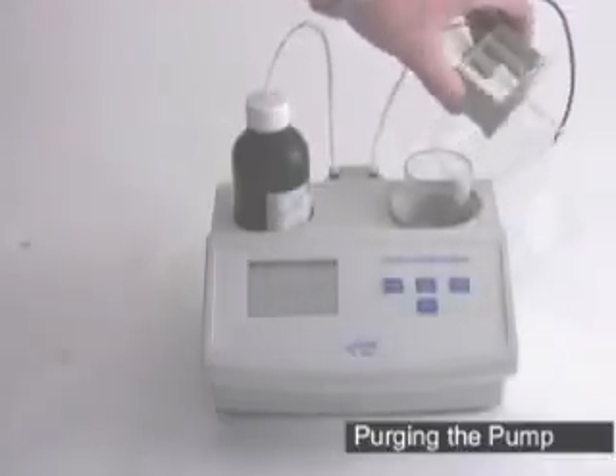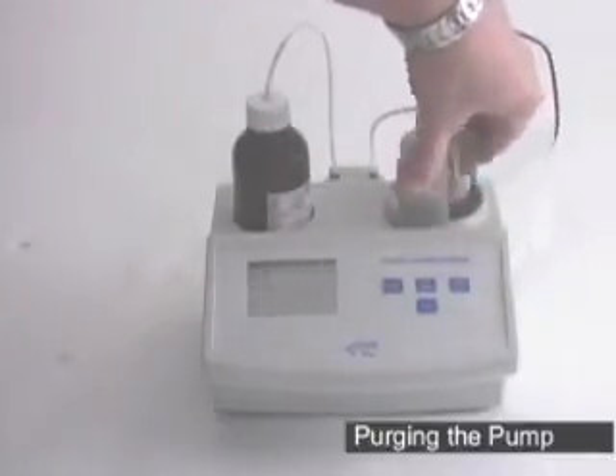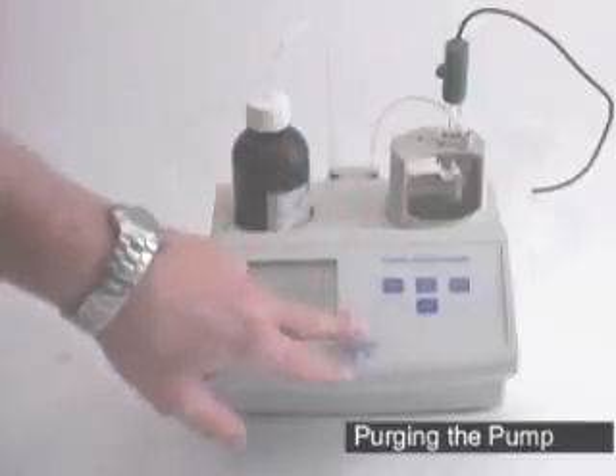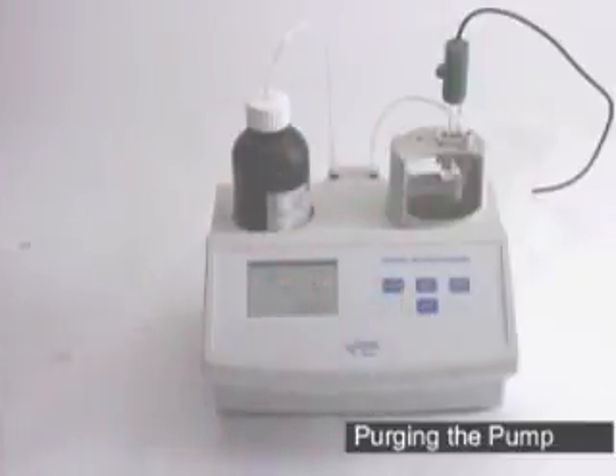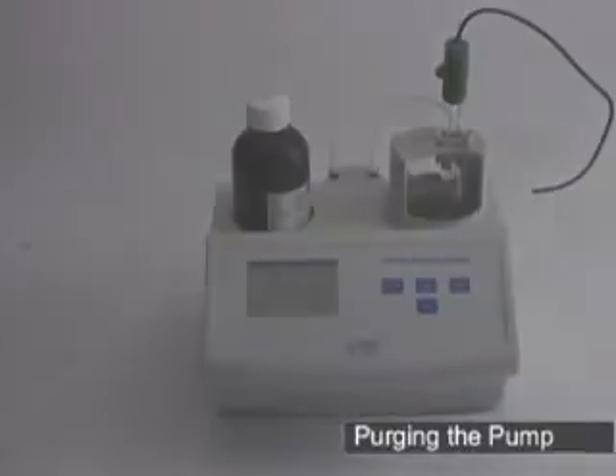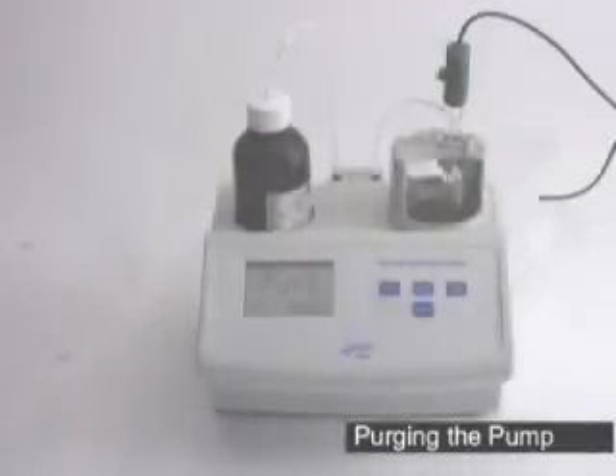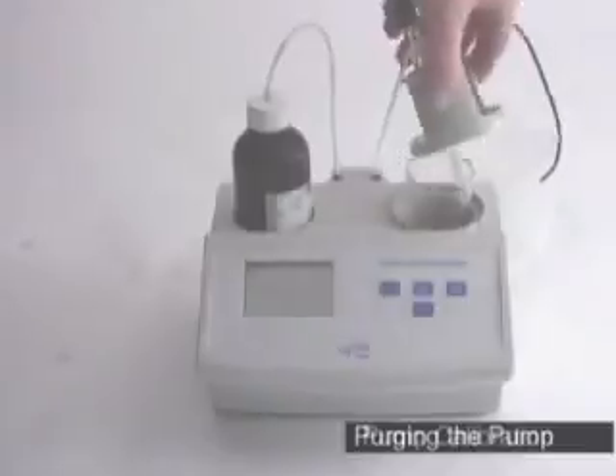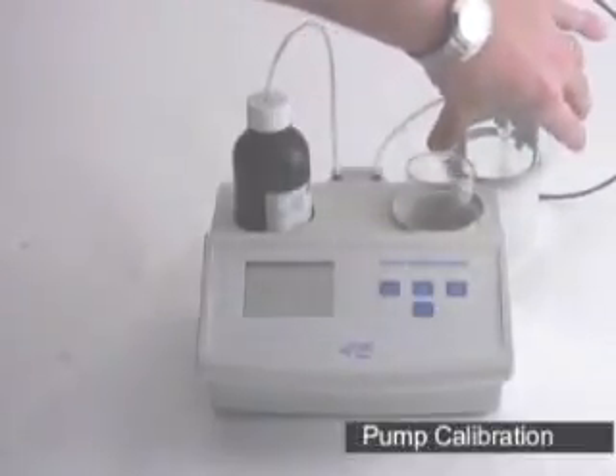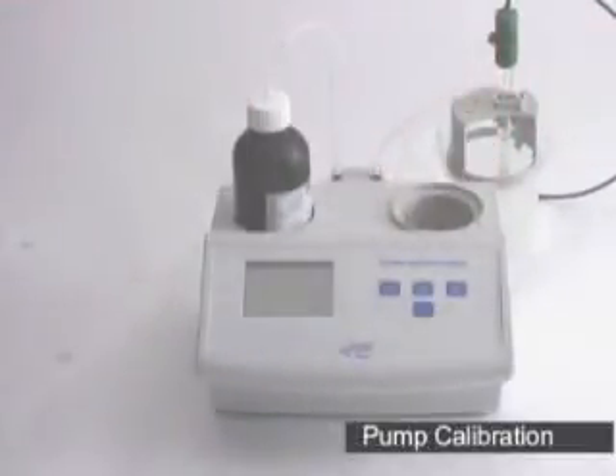Put a beaker into the machine, replace the cap and tubing. Make sure your tubing is down into the beaker and press the purge button. Purge cycle will run for 5 minutes, which will make sure there's no air left in the line. Once the purge cycle is done, we're going to remove the cap and move on to pump calibration.